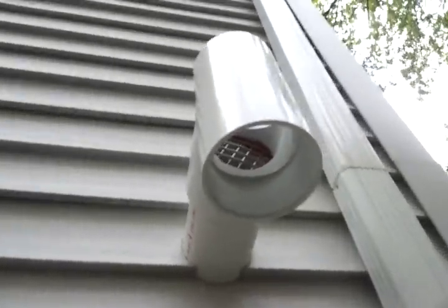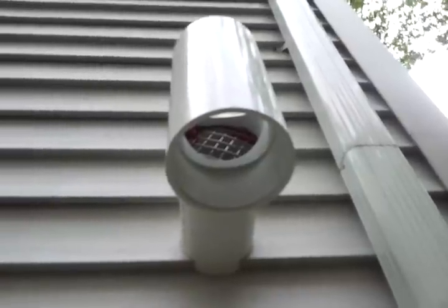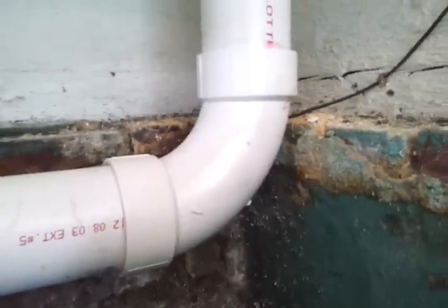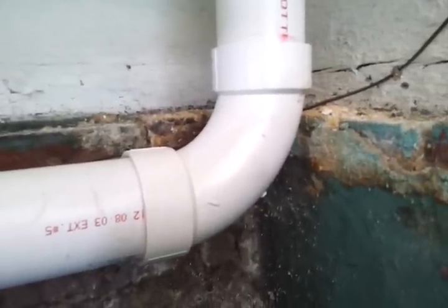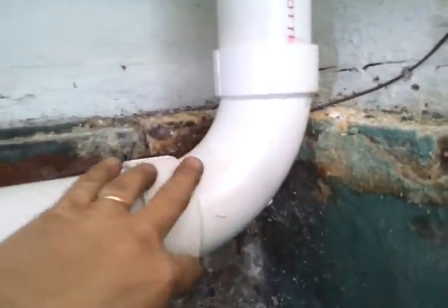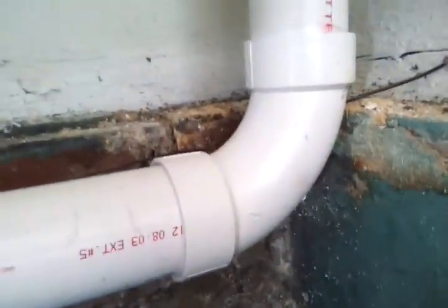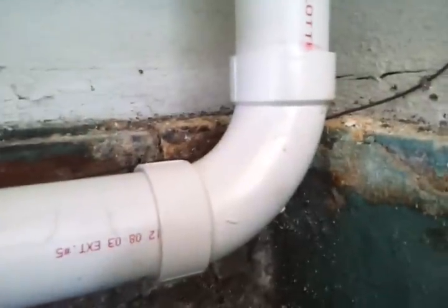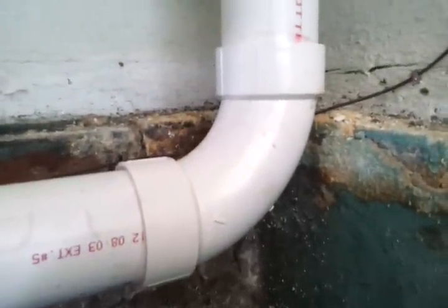This is our exhaust terminal. As you can see, there's a rodent screen way up inside that T. In any sealed combustion appliance you always want to use long-sweep 90s, and that's what these are — this is a three-inch long-sweep PVC 90. Never use a short-radius 90 on these sealed combustion units.